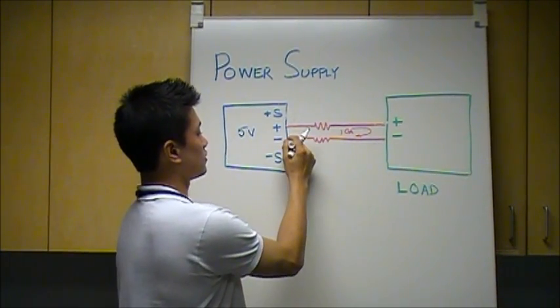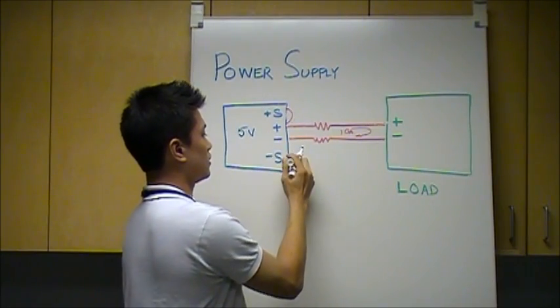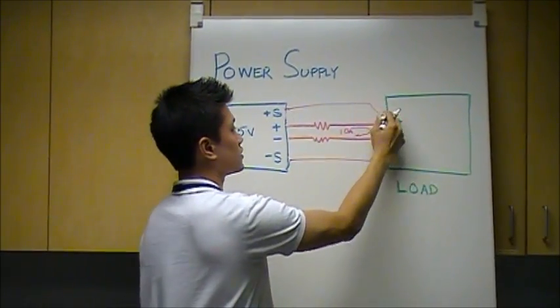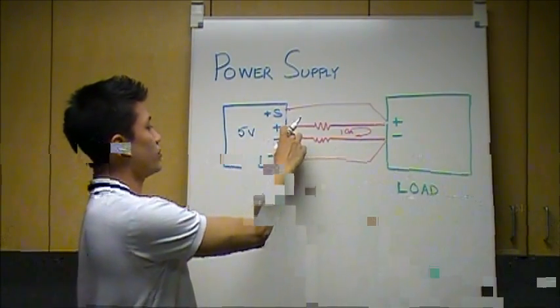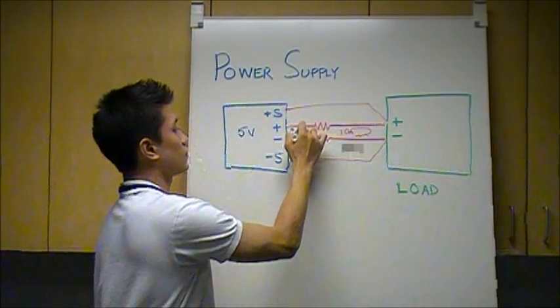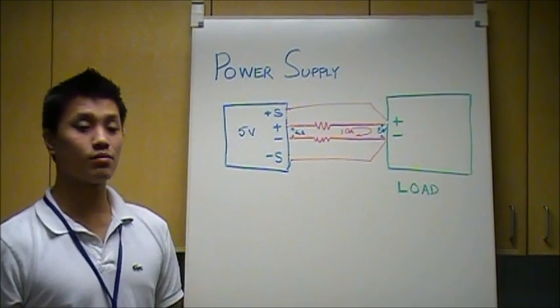To correct that, we disconnected the plus and minus sense terminals from their original local sense connection and connected them using remote sense directly to the load. This allowed the power supply to output 5.3 volts at the plus and minus output terminals, resulting in exactly 5 volts at the plus and minus input terminals of the load.